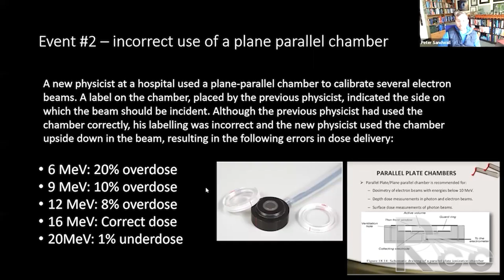There was the incorrect use of the plane parallel plate to measure the electron beams, but the contributing factors were that this individual did not know how to use that chamber. So they used the chamber unfamiliar without verifying the proper technique. And always get the manual for a new chamber, whether it's a PTW, a Standard Imaging, an IBA, or whatever chamber. I'm sure there are others that I'm unfamiliar with. Get the manual. It's very important.